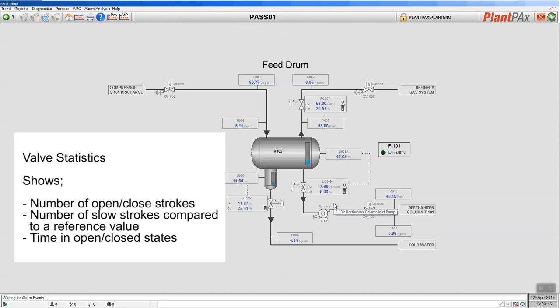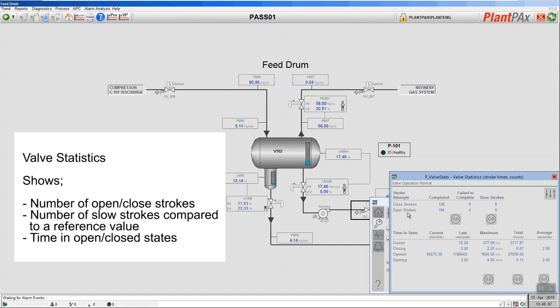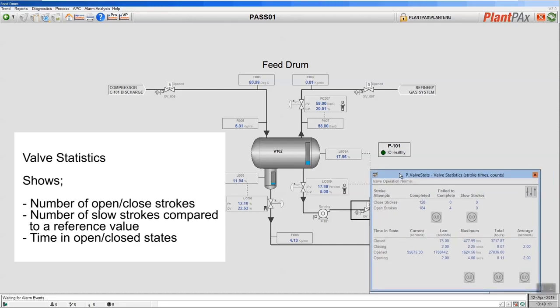Now let's look at the statistics object for a valve object, which is available for both a two-position valve and a three-position valve. I'm going to go into the faceplate for that valve and then into the maintenance tab, where I can access the statistics information for that valve. For a valve object, the statistics object collects the number of times the valve has been moved from open to closed or closed to open, the number of times that move may have failed, and the number of times there has been a slow move — where the move took longer than a configured value. It also generates statistics for the amount of time it's been closed, the time taken to close, the time it's been open, and the time taken to open.